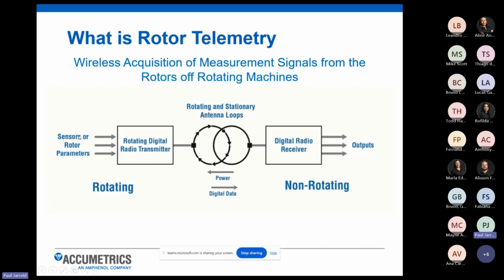So we take that sensor parameter, it gets connected right to the rotating digital transmitter, which would be mounted on the shaft and spinning with the equipment. And then that rotating transmitter essentially has a hoop of wire that forms a rotary transformer connection between the rotor and stator. As long as that's in close proximity and coupled close by to the stationary hoop, we're communicating data off of the rotating shaft. So we bring data off the rotating world through one hoop of wire to a stationary hoop of wire. And then that gets connected via cable to our digital receiver. And then we provide the outputs to the customer from our receiver unit.